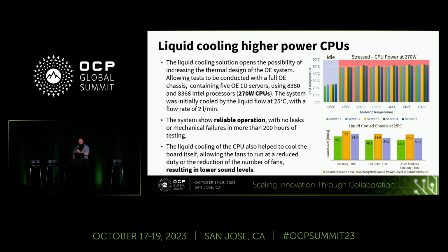If you look at the chart on the right, anything below 50 decibels can be considered office equipment level. You'll see in the far right graph the green is at 48.8 with 2 fan modules at 10%. So we can cut the fans down quite a bit, which cuts down a lot of the noise, getting this into a decent area - even audio pollution, if you will. So it's not just heat pollution, but audio pollution as well.